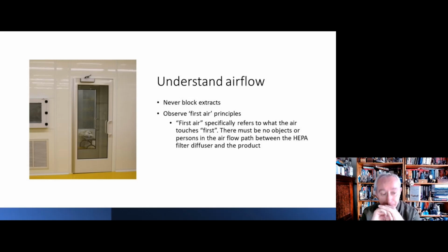And you need to never have any exposed product or vials where you might be breaking the principle of first air. With first air, the air is clean. Whatever the air touches first is called the first air principle, and we want to make sure the clean air is still touching the objects that we're trying to protect first.